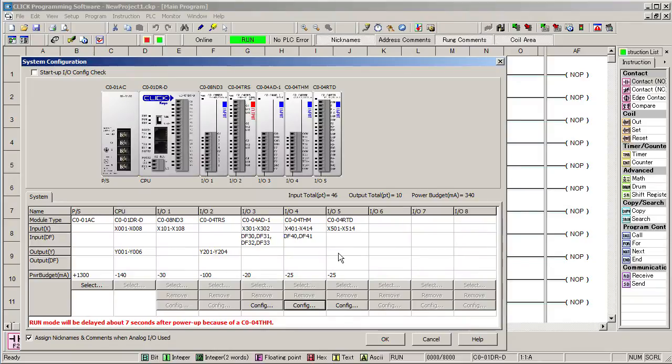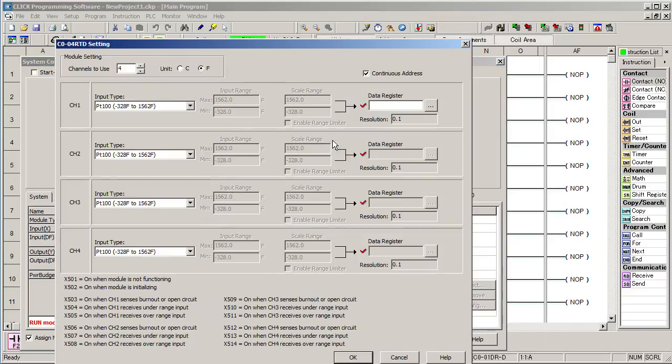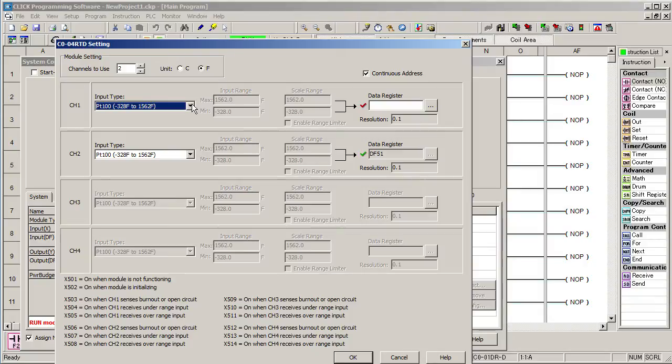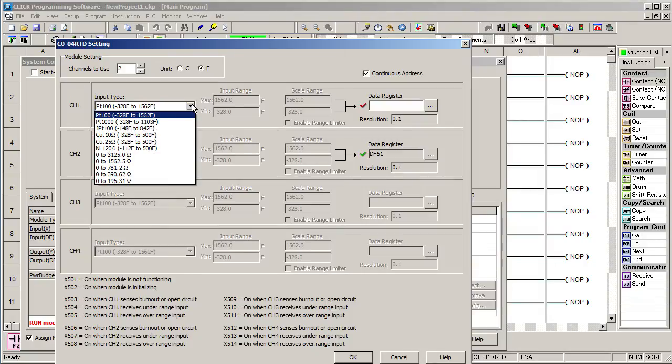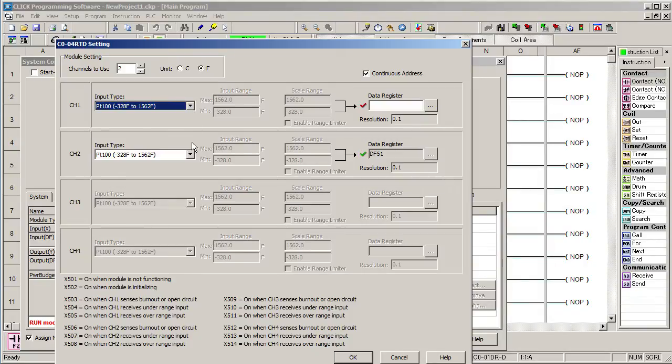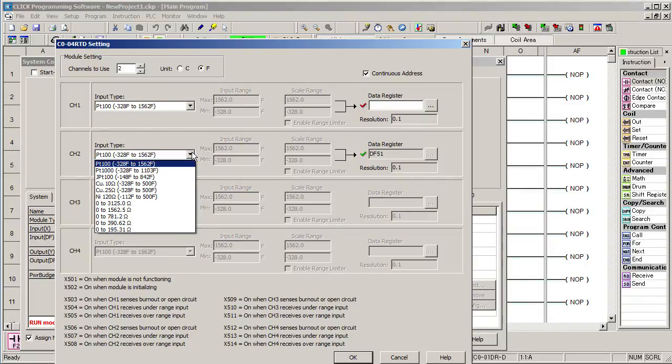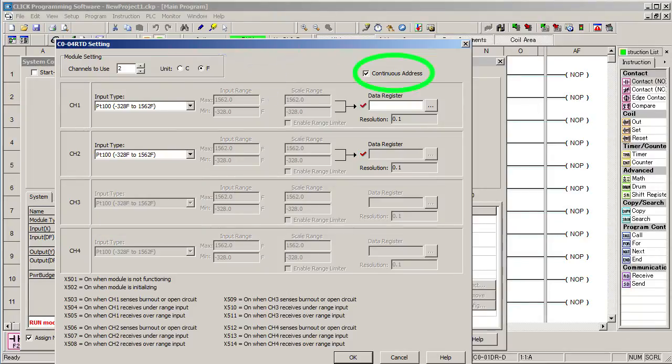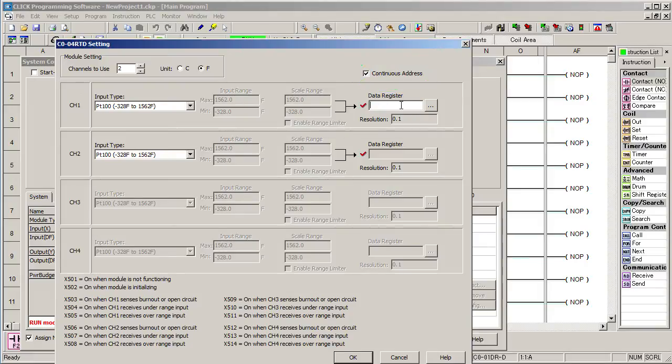Ok, finally, let's configure the RTD module. Here's a little trick. Instead of clicking configure, you can also just double click on the module. We're using two of the RTD channels and we want the results to be in degrees F. Both RTDs are PT100s over this temperature range. This module supports all these kinds of RTDs and just like the thermocouple module, you can specify a different RTD type for each channel. We'll use this option again and let's start the RTDs at memory location DF51.